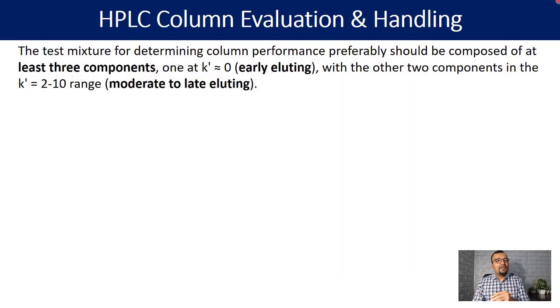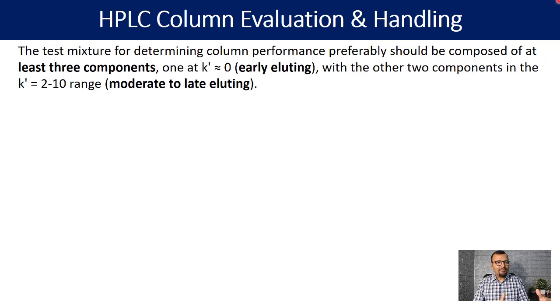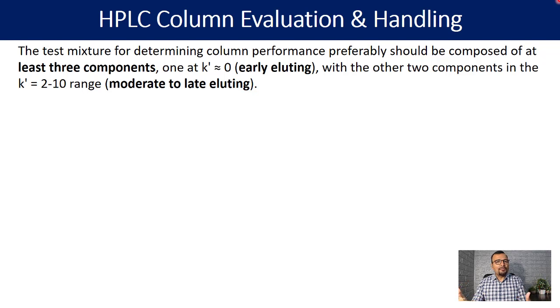It is always preferred to have a column performance mixture containing at least three components. One component should be eluting very early and two components can be eluting quite late. This is going to help you in understanding the retention behavior on your column for three different types of components.